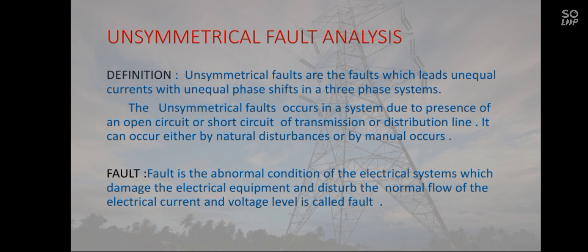Unsymmetrical fault analysis. Definition. Unsymmetrical faults are the faults which lead to unequal currents with unequal phase shifts in a three-phase system. The unsymmetrical faults occur in a system due to the presence of an open circuit or short circuit of a transmission or distribution line. It can occur either by natural disturbances or by manual causes.